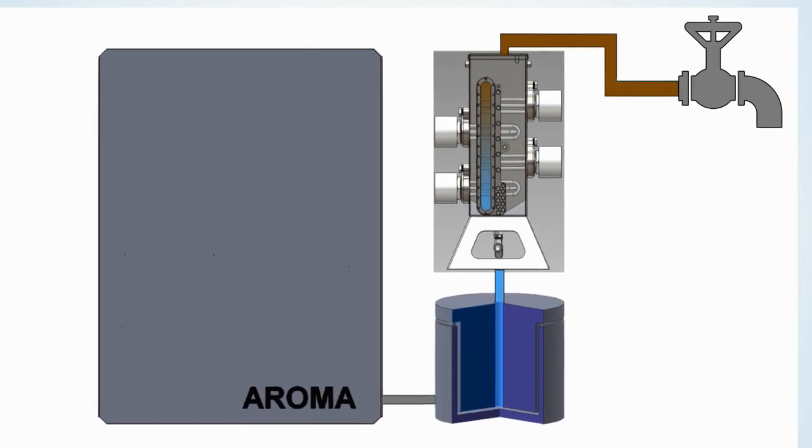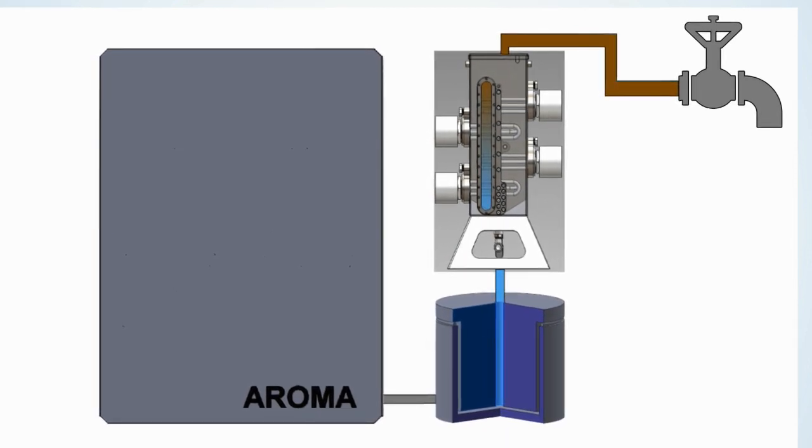Once the water cut is isolated, the tracer chemicals are extracted from the water using a specially developed thin film. After extraction, the film is heated to high temperatures releasing the tracer chemicals as vapors that are passed directly to the Aroma Sensor. This process eliminates the chemical preparation steps required during manual sampling.